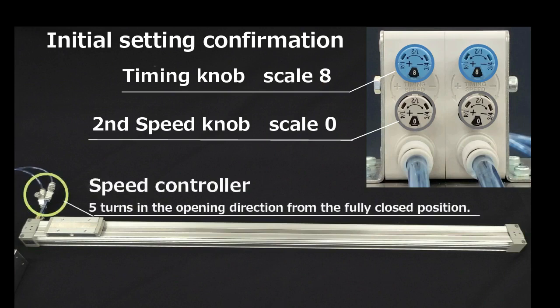And the speed controllers for adjusting the first speed must be set to a position 5 turns in the opening direction from the fully closed position.